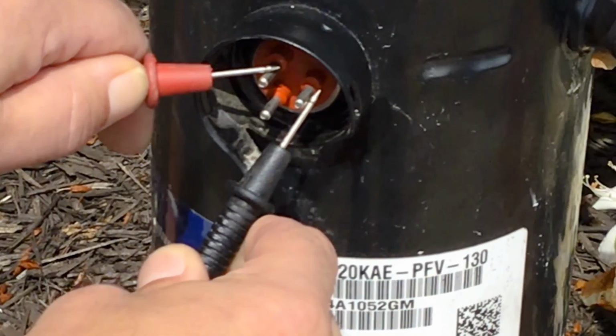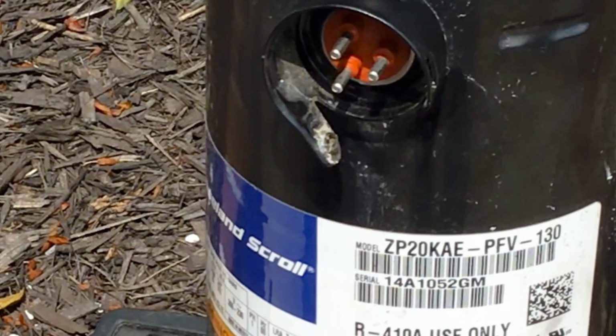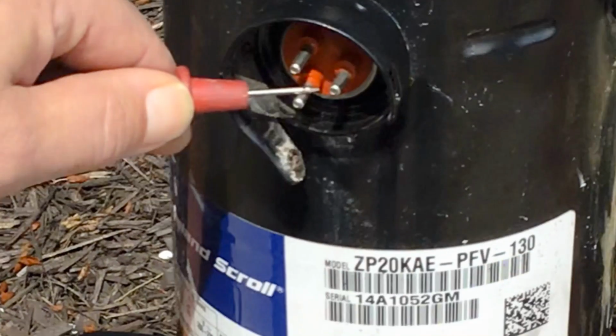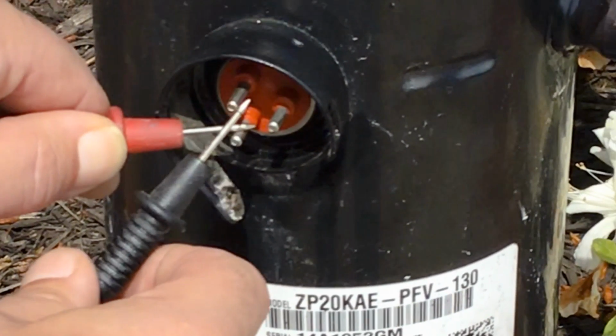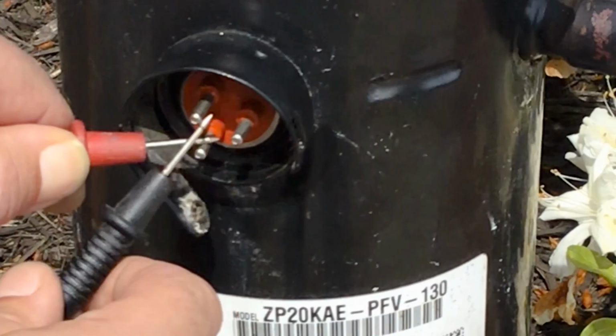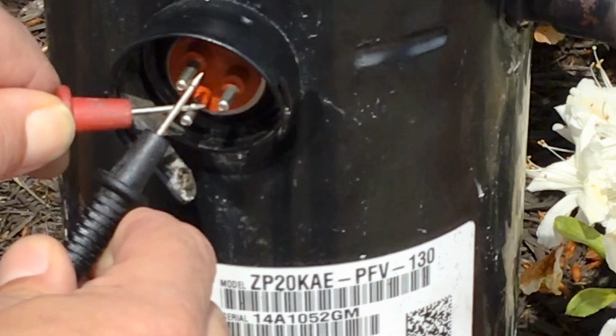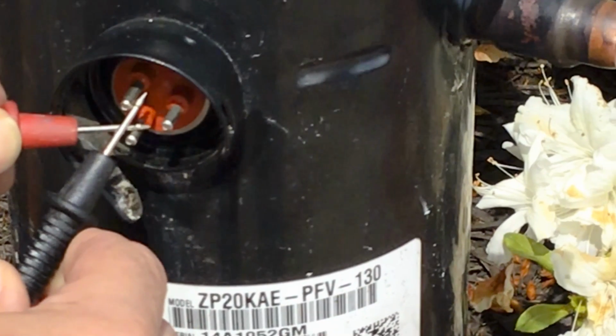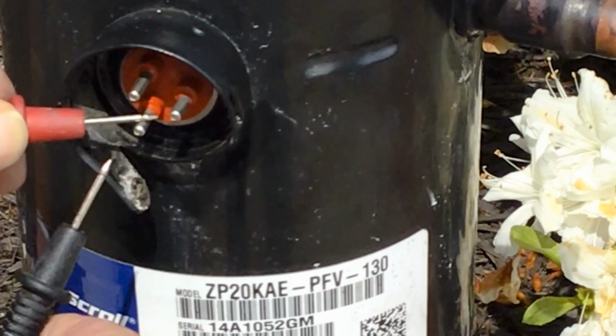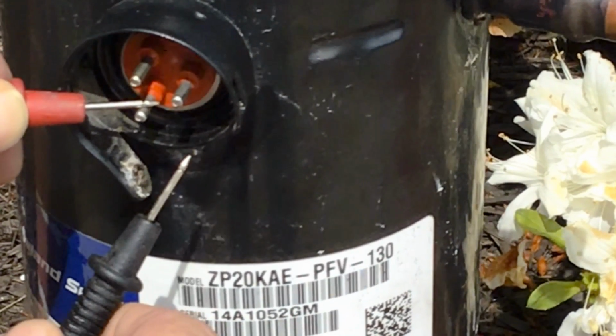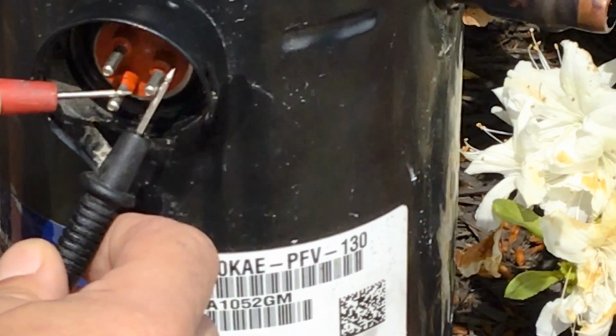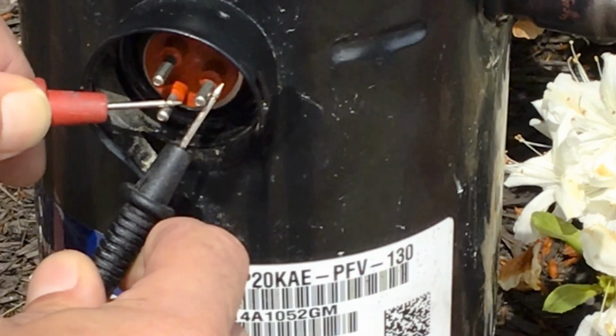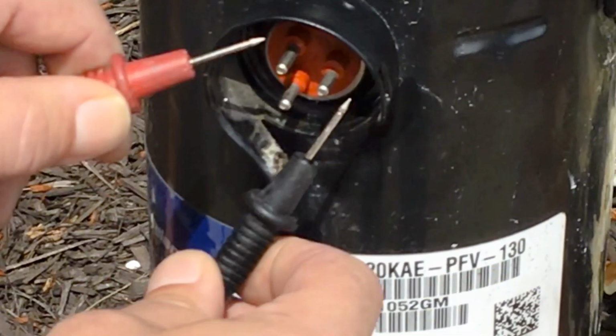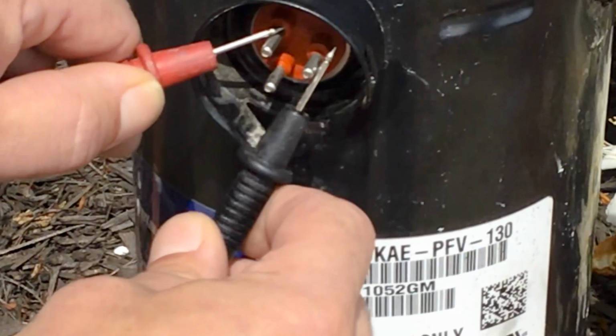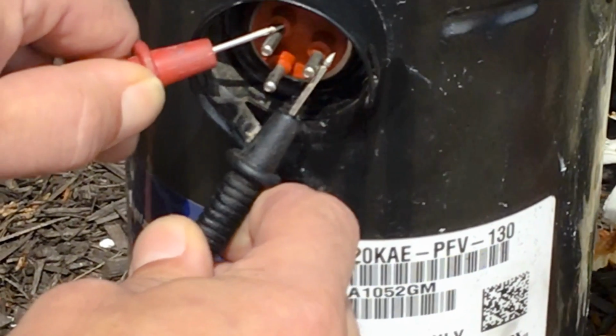Now, at the same time, just to use simple math, if my lowest reading, which should be common to run, happens to be 5 ohms, and then my middle reading, common to start, happens to be 10, then your run to start should be 15.